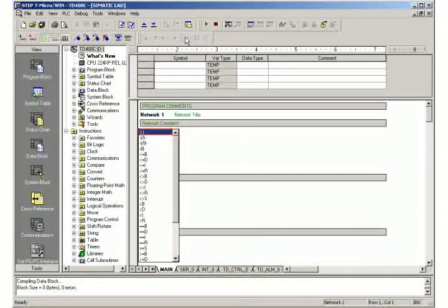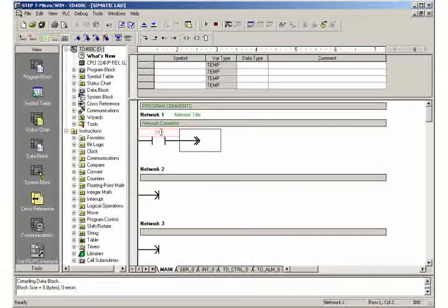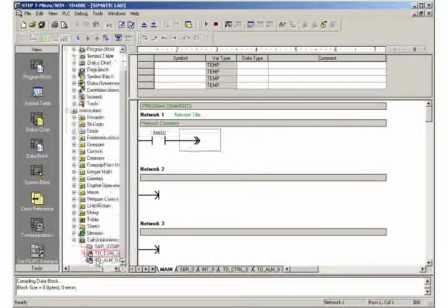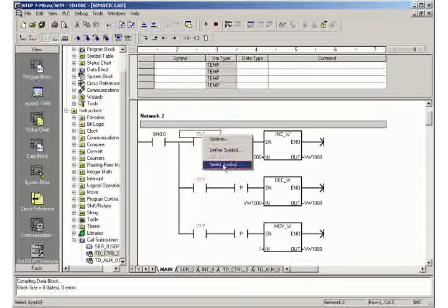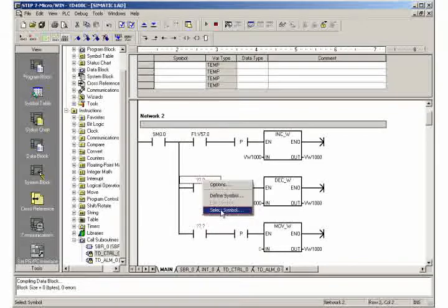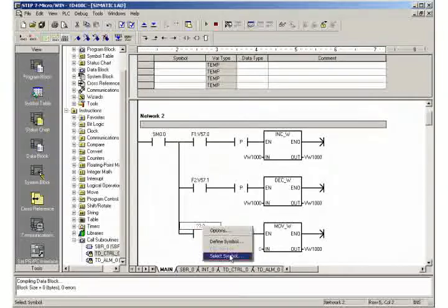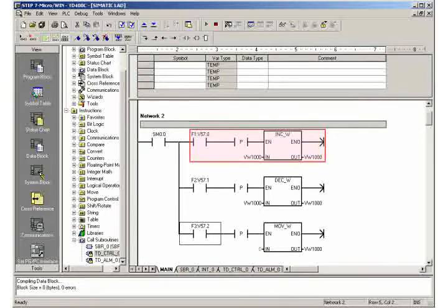Step 2: Creating the program code. Call the control subroutine generated by the text display wizard on every scan in network 1 of the program. Program the actions of the function keys in network 2. You can find the corresponding bit addresses by right-clicking and selecting the symbol. The value of the chosen data address VW-1000 will be incremented by pressing F1, decremented by pressing F2, and reset by pressing F3.